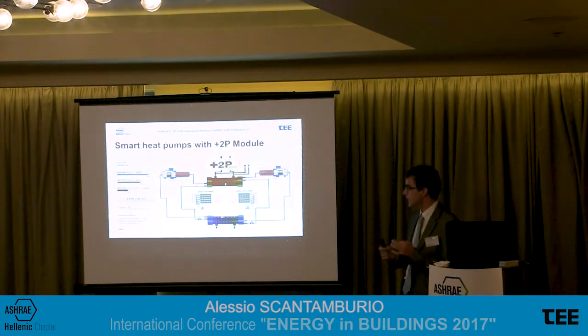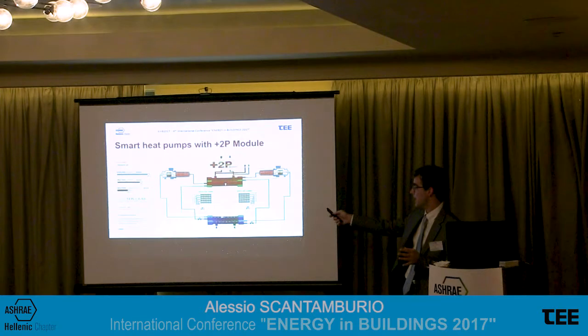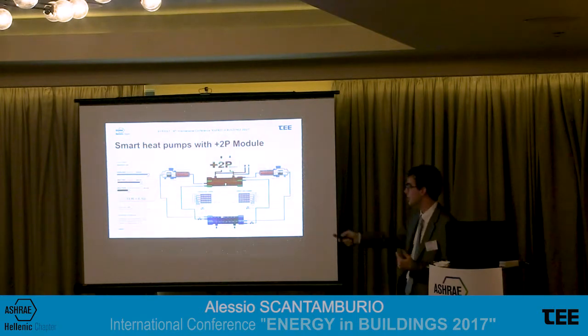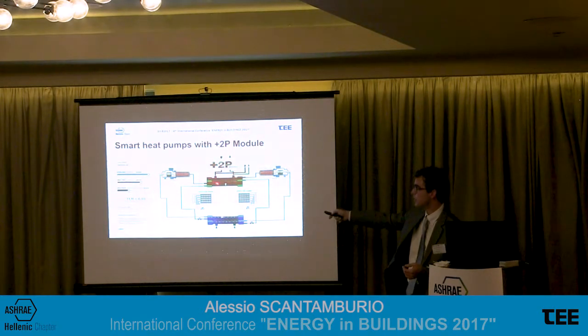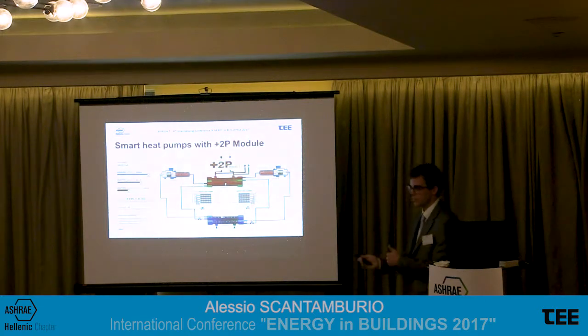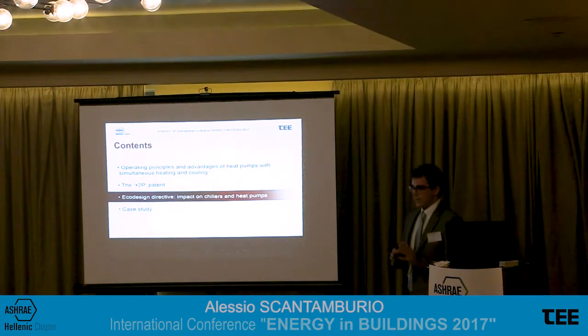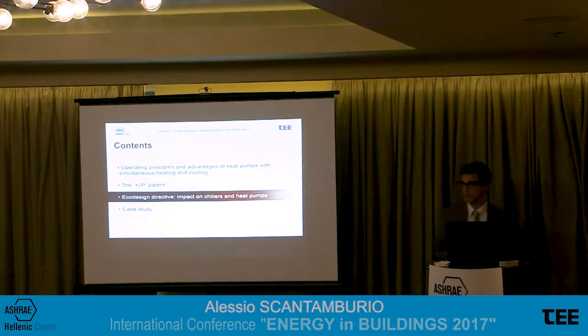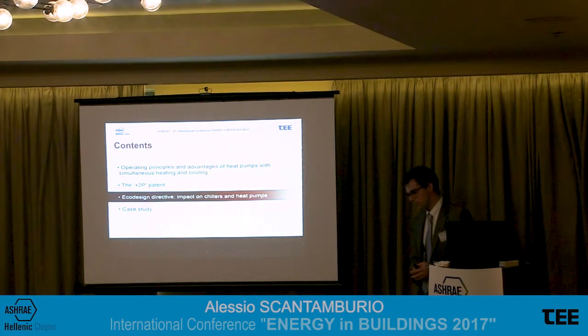And of course, the only limit in this case is the fact that, as we are sending part of the medium temperature hot water to the additional water-to-water heat pump, here available for the building, I would not have the total heating capacity produced here, but of course, it is a matter of calculation. Okay, this is the technical content of the 4-pipe unit and technologies for enhancing even more the temperatures on the hot water side.